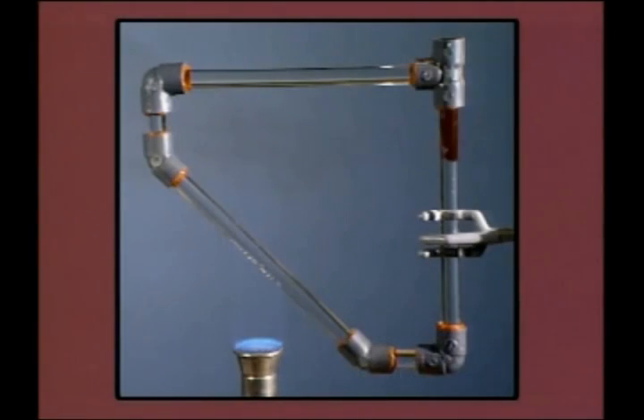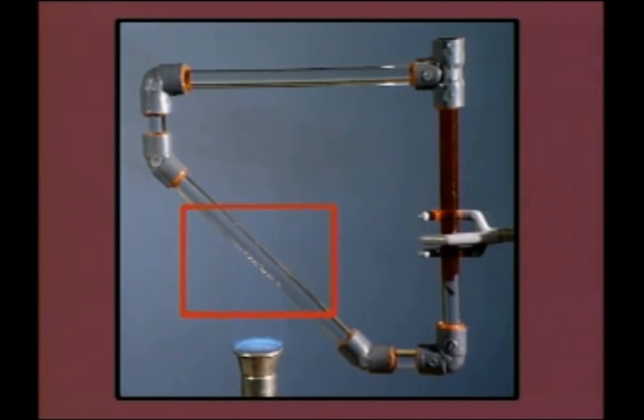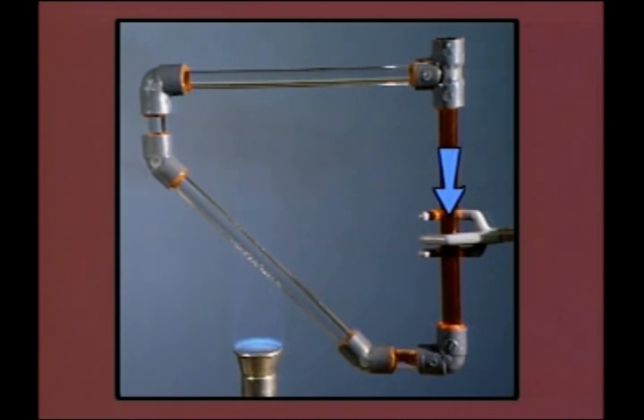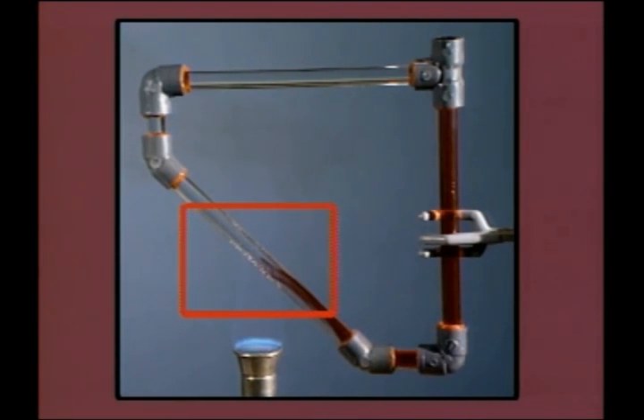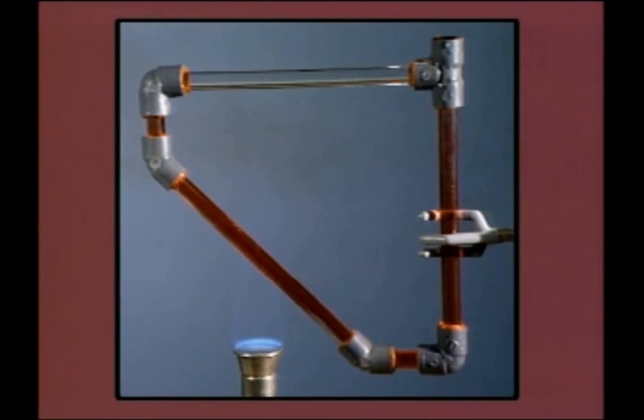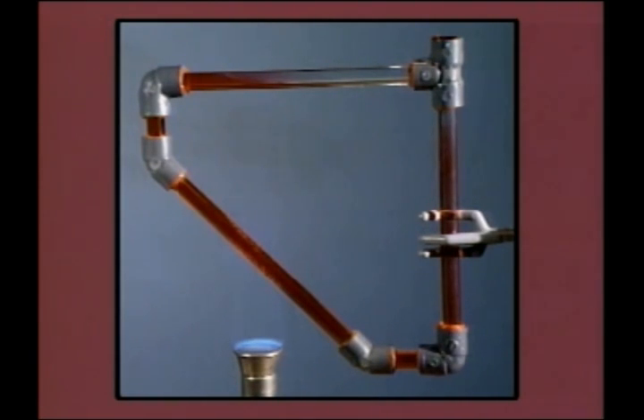The type of convection depends on what produces the fluid movement. In natural convection, when one side of a loop is heated, the fluid in that side gets lighter — less dense — and the warmer, lighter fluid rises. It's replaced by cooler, denser, and therefore heavier fluid coming in behind it. The difference in density between the warmer and cooler water starts the flow. When more heat is added, the temperature difference increases and the flow rate increases; if the temperature difference decreases, the flow rate decreases.